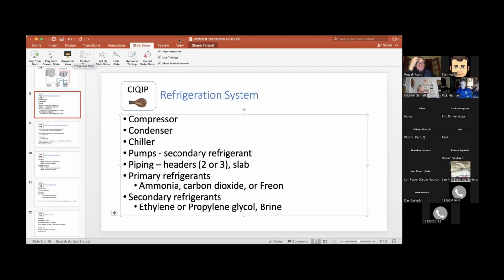Propylene glycol is supposedly very environmentally friendly compared to ethylene glycol. They're both good. They have good properties, but propylene glycol has a viscosity shift as the temperature drops. So it goes from a very thin material to a much thicker material as it gets closer to the freeze point of the glycol and water mix. Ethylene glycol has almost no shift in its viscosity through the range of temperatures that we operate.